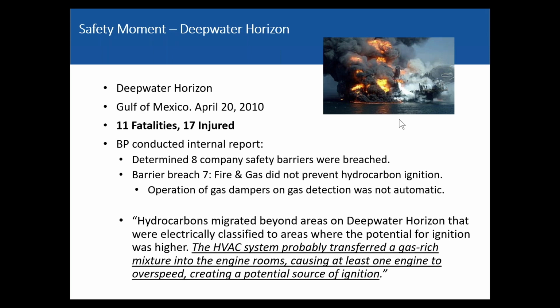And they talk about operation of gas dampers. Oh, boy, that's HVAC stuff. One of the quotes out of it was: the HVAC system probably transferred a gas-rich mixture into the engine rooms, causing at least one engine overspeed, creating a potential source of ignition. So electrical area classifications, safe areas, we're going to talk about this in a little bit, but you have safe areas and hazardous areas, and gas went from the hazardous area into the unclassified area where you have arcing and sparking of equipment, and explosion, bad stuff.